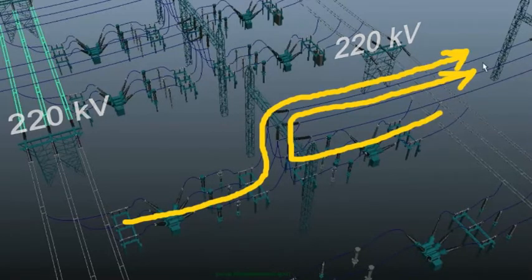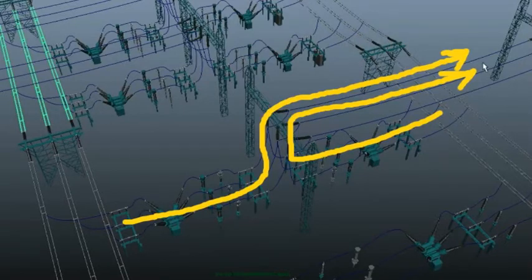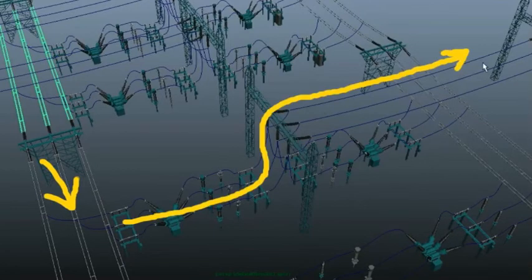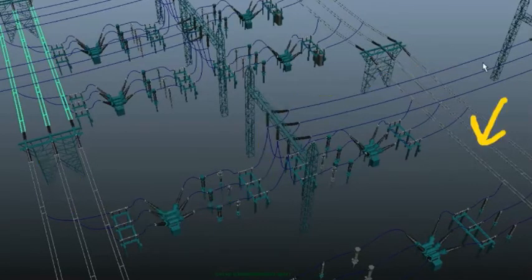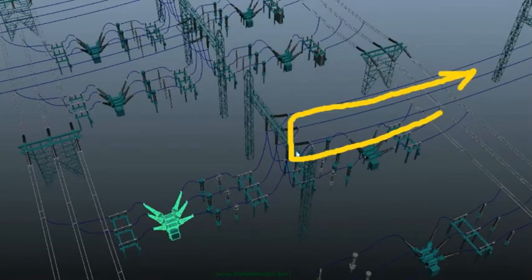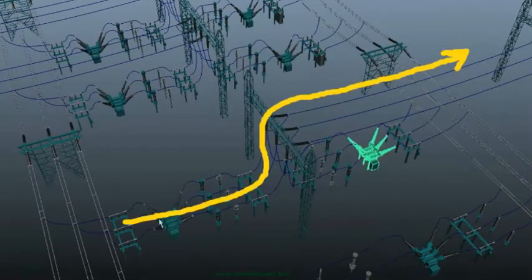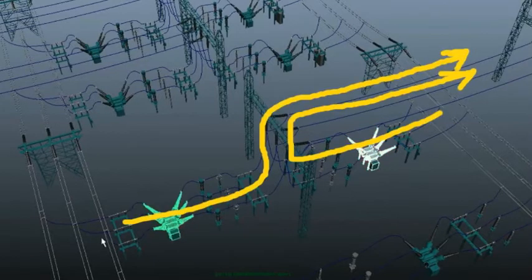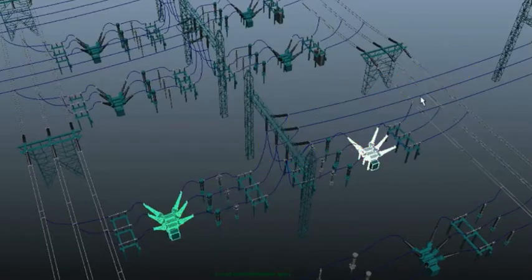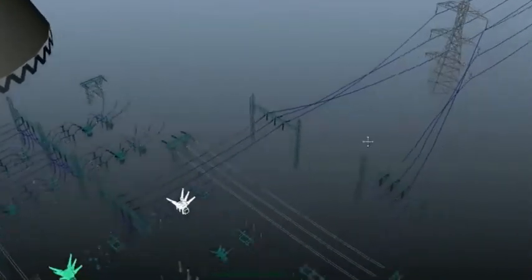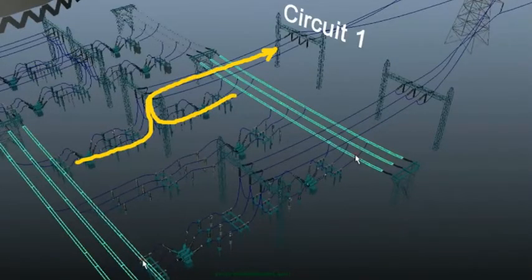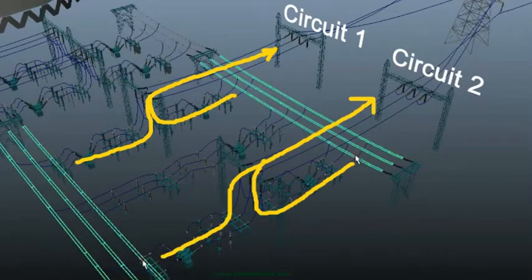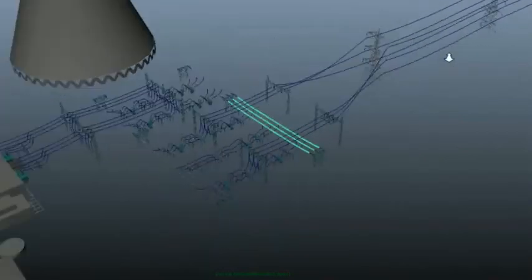Now, a connection has been taken out for further transmission of electrical power. So, from this bus, we take the connection through this path, and from this bus, our supply will go through this path. If this circuit breaker is switched off, then the power will continue from this path, and if this circuit breaker is switched off, the power will choose this path. If both the circuit breakers are on, then power will continue from both the paths into the transmission line for the next destination. This is the first circuit of the transmission line and this is the second, for which we have the same arrangement. Here we have 3 line conductors for the second circuit and similarly 3 line conductors for the first circuit.